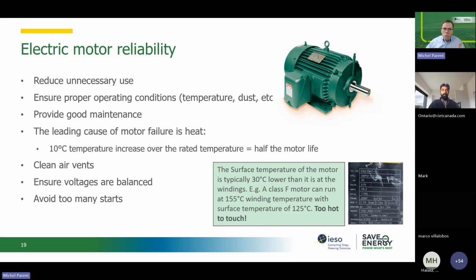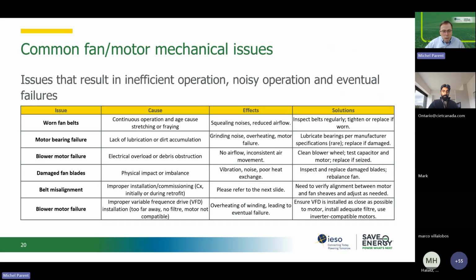Like I said, we need to remember motors don't like heat, and that is one of the reasons when you have a VFD, you don't want to slow it down too much, especially if that motor is running in an enclosed space without proper ventilation, and it's, let's say, a hot water pump. It's already hot because of the liquid that's in that pump. So that motor can actually get even hotter. And if you run it at 10 hertz, it's likely going to overheat the winding. So those are the things to look for when you're talking about the actual motor reliability in regard to its temperature.